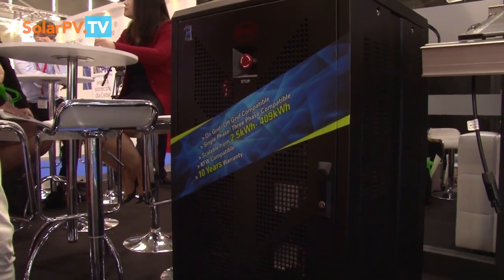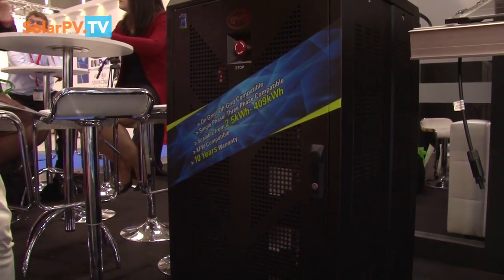Which is the application for this? It's similar, but it's battery only. That means if you want to build a system, you need inverters and the connections, because in the market some suppliers offer only batteries. So the customer needs flexibility to select either DC only or the full integrated system. The size is up to 12 kilowatt hours with different numbers of battery modules. Depending on customer needs, it's scalable — each unit is 2.5 kilowatt hours, so 5, 7.5, 10, 12 — it's scalable.